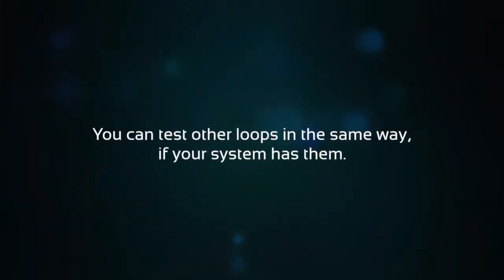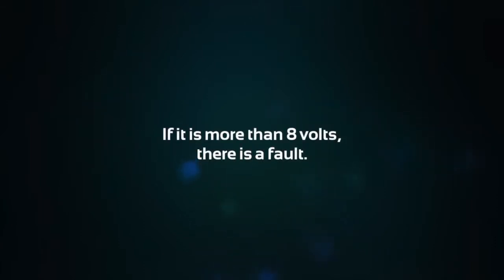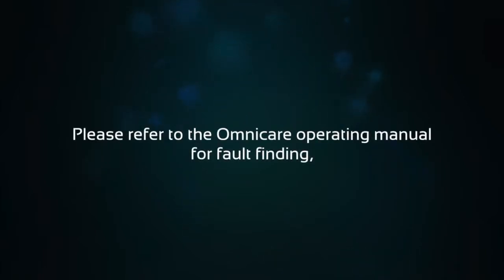You can test other loops in the same way if your system has them. If it is more than 8 volts, there is a fault. Please refer to the Omnicare operating manual for fault finding.